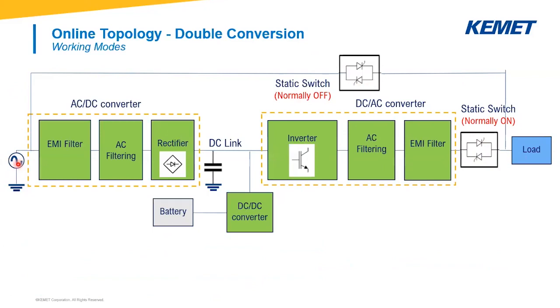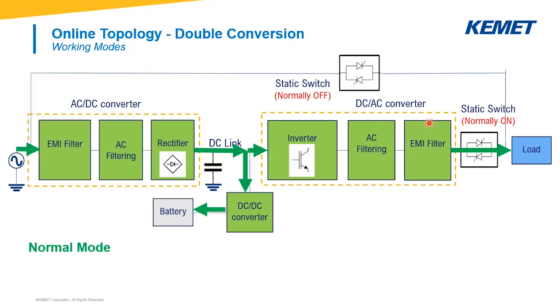Let's go more into detail on all the working modes. We have, first of all, the normal mode — that is the mode when mains is up and power comes from normal utility. Power comes from the input; on one side it goes to the battery to recharge it, and on the other side it goes to the inverter, then through AC filtering, EMI filtering, and finally to the final load.